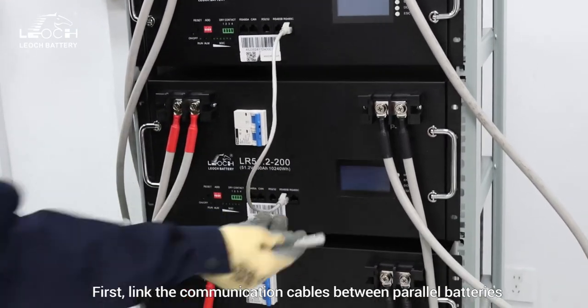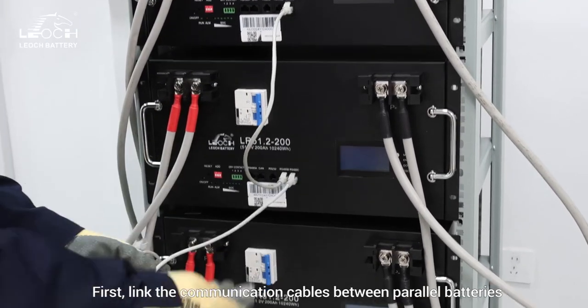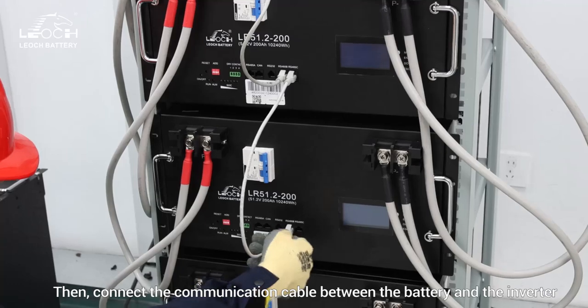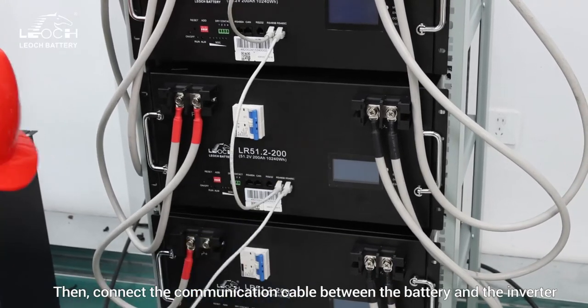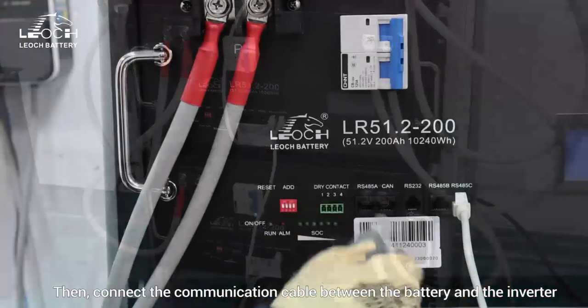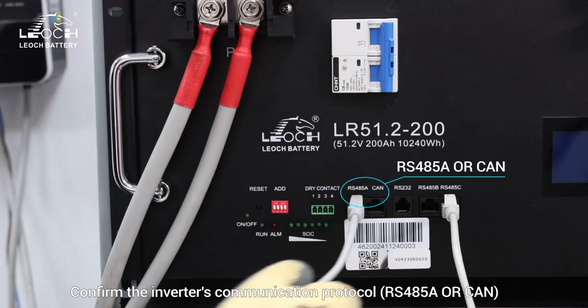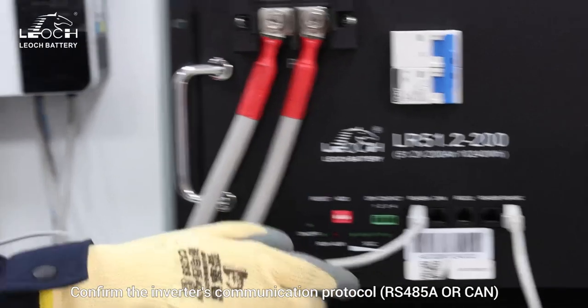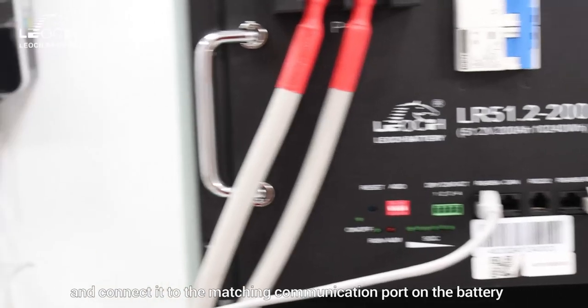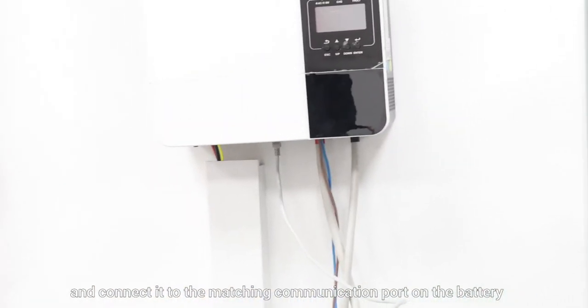Testing and commissioning. First, link the communication cable between parallel batteries. Then, connect the communication cable between the batteries and the inverter. Confirm the inverter's communication protocol, RS485 or CAN, and connect it to the matching communication port on the batteries.